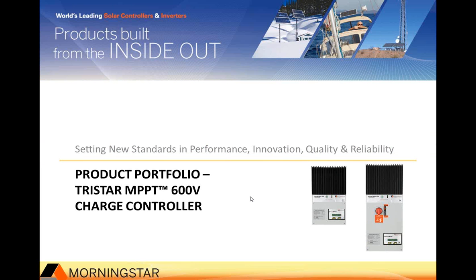What we'll be talking about today is the TriStar MPPT 600 volt controller and the ground fault protection device. This product is used in conjunction with the TriStar MPPT because, of course, for U.S. electric code, a ground fault protection device is required when you have an array on a dwelling. So we're offering both of those products.